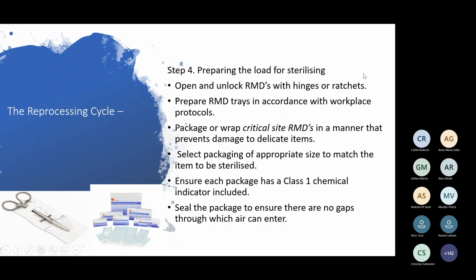Okay, step 4 is preparing the load for sterilizing. Another question we get asked all the time: do I need to have my instruments wide open? No, you don't. You need to have them open slightly and unlocked. So anything with a hinge or ratchet needs to be unlocked. They don't need to be spread wide apart. They just need to be open so that the steam can penetrate into the box joint.